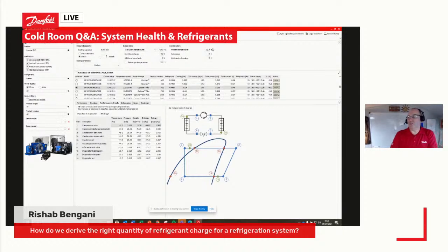So this is a very good way to double check on site when you're commissioning a system, to make sure that your suction pressure, discharge temperature, liquid temperature, etc. is there or thereabouts where it should be. So yeah, it's something that I use quite a bit when I'm on site with condensing units, just to double check that it is what it is. So yeah, that's Danfoss Cool Selector software. So I hope that answers that one. Let's just, I'll stop sharing as well. So hope that answers that question.